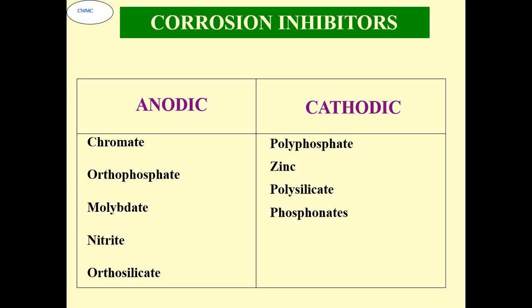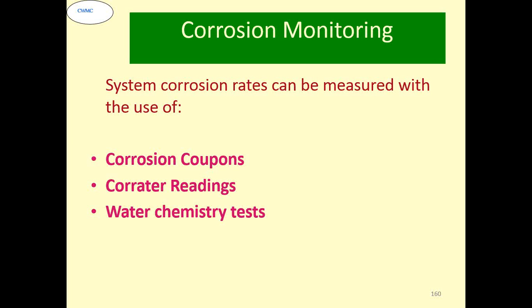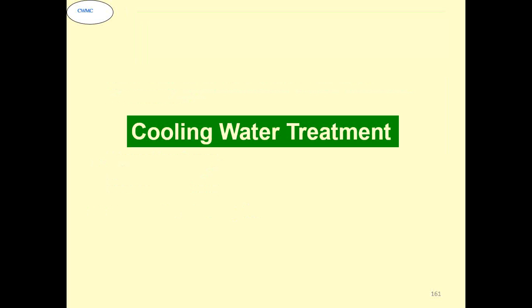The anodic type of these are chromate, orthophosphate, molybdate, nitrite, orthosilicate. Orthosilicate is considered suitable even for drinking water. Phosphate is again suited for drinking water, where the normal limit is about 5 ppm. Polyphosphate, zinc, polysilicate, polyphosphonates, they are all cathodic inhibitors. Monitoring can be done through corrosion coupons, corrater readings, or water chemistry tests.